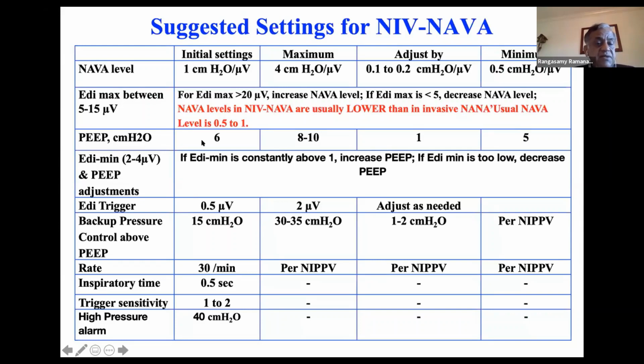PEEP, standard, 6 centimeters. You may increase it to 8 or 10 if the lung is not well recruited, and minimum PEEP you want to keep around 5. EDA minimum, normally it's around 2 to 4. If the Edi minimum is consistently above 1, you can increase the PEEP. That means the lung is not well recruited. If the EDA minimum is too low, less than 1, then decrease the PEEP. EDA trigger, as I said, 0.5. Rarely we have to go up to 2. In a big baby who's very active, keeps constantly triggering, you may go to 2. Adjust as needed.